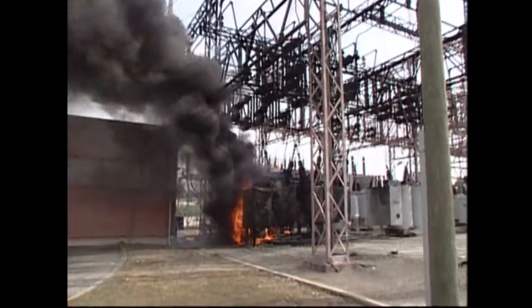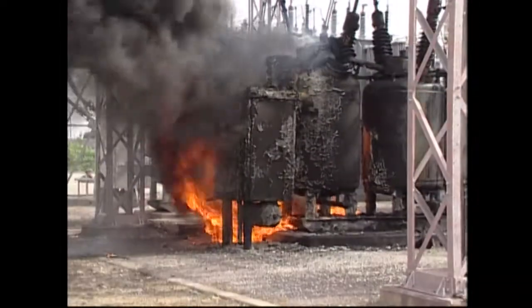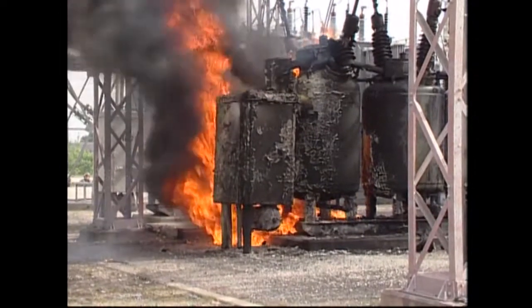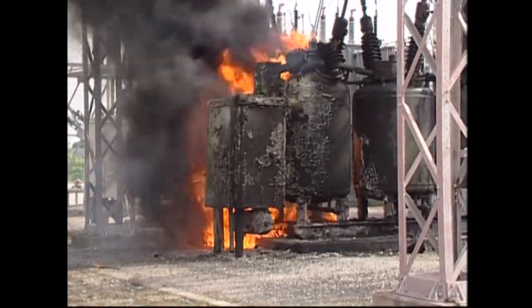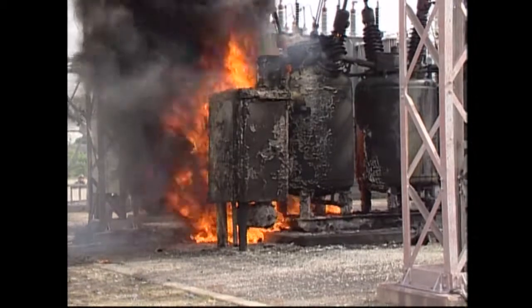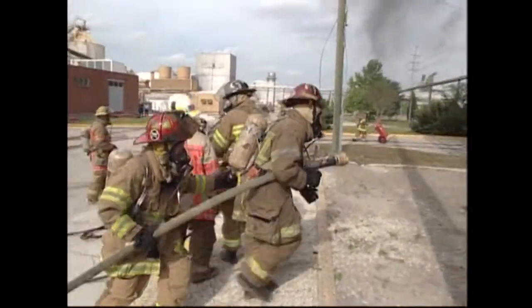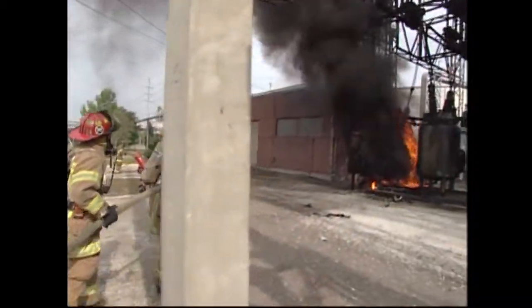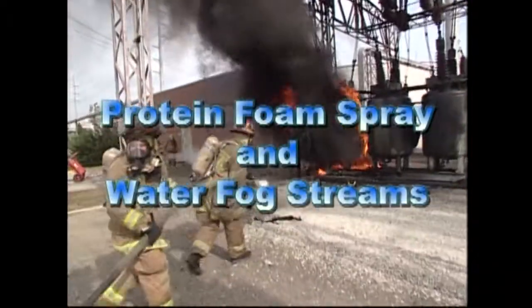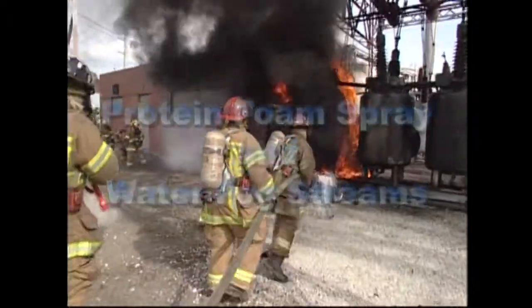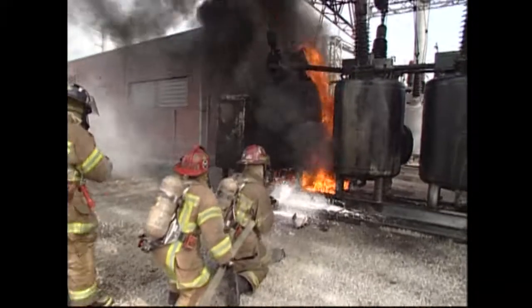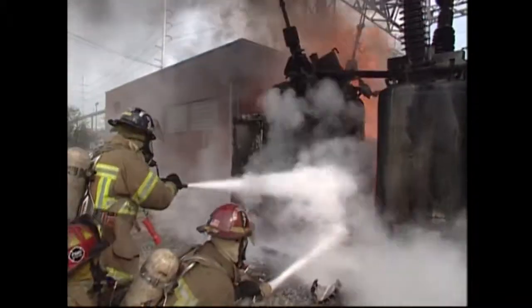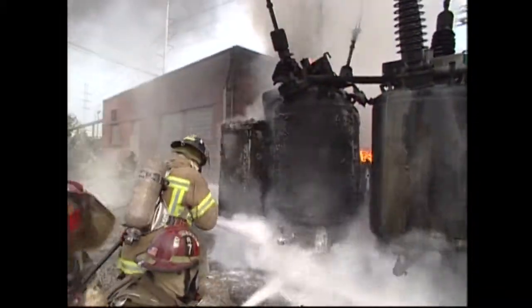Most times the fire is coming from oil in circuit breakers or transformers. Because large amounts are housed inside, it's a major concern which requires special guidelines. With equipment de-energized, the oil fires can be extinguished by using protein foam sprays and water fog streams. Never use a solid stream of water on oil or any pools of oil, which could actually spread the fire.